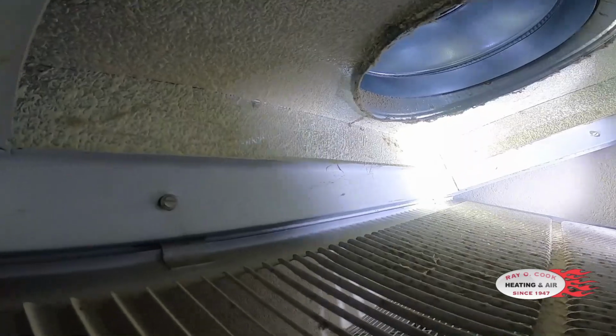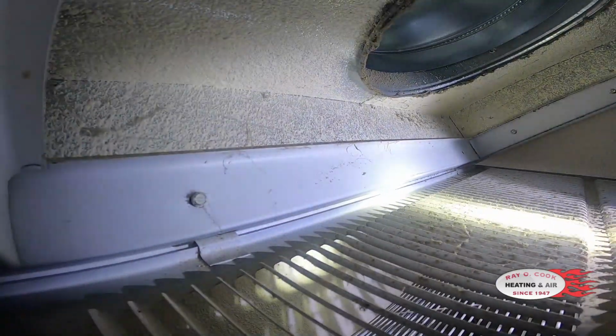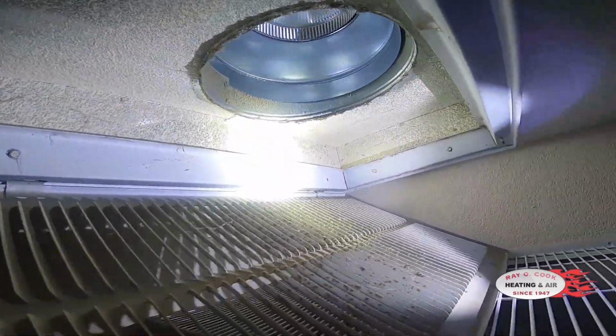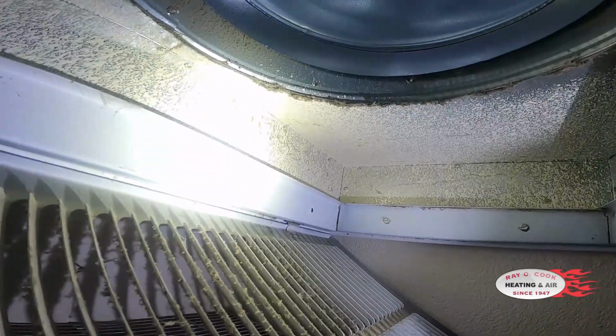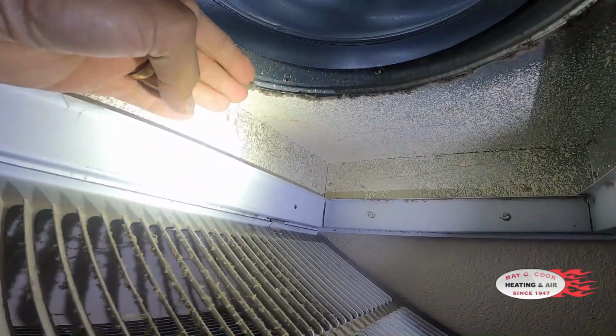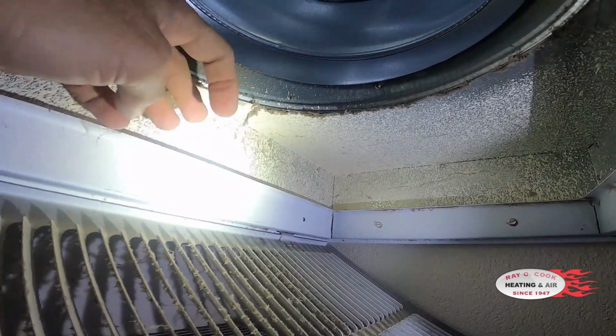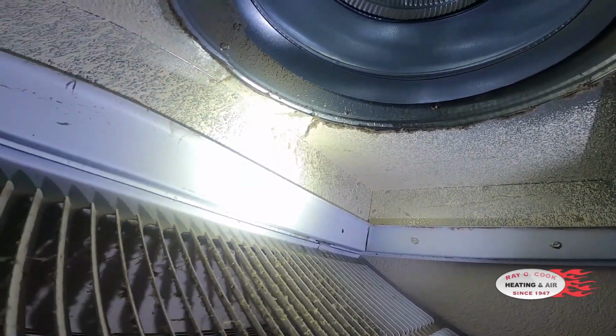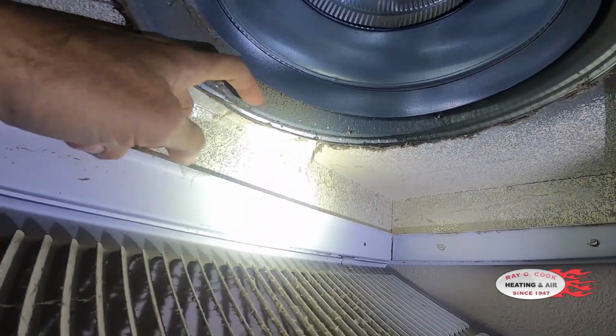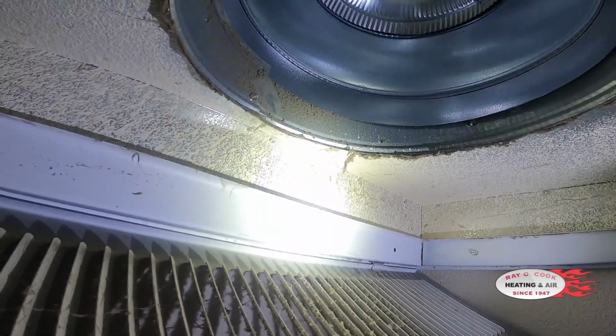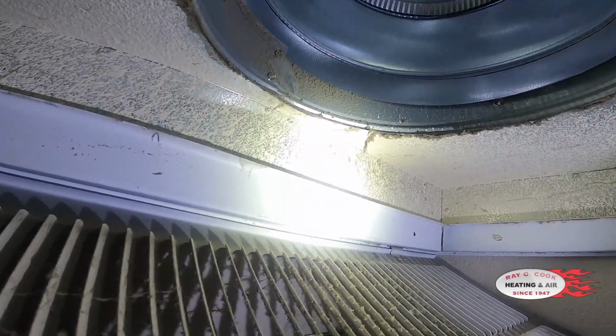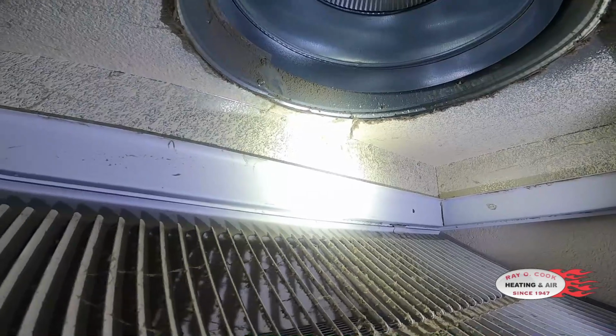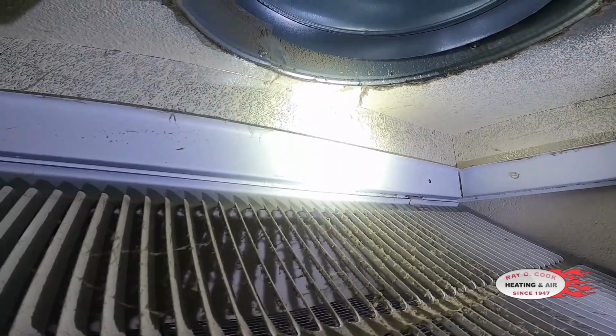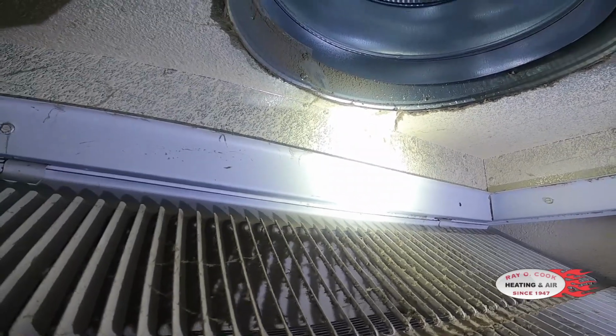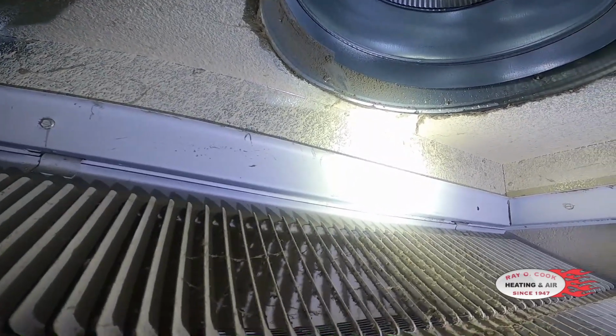So you can clearly see all of the dust there on the unit side of the filter. Now here we have even more dust at the duct. So you can see all of that is past the filter up inside the ductwork. You can see it here. It's basically falling out of there, and that's air that you are breathing because it's past the filter. The filter did not catch it. So a perfect example, that filter that I just took out of there was a MERV 11, and a lot of its air was going right by the filter.